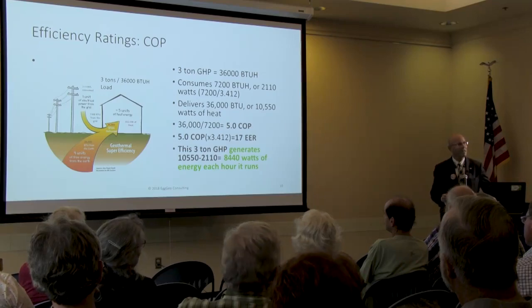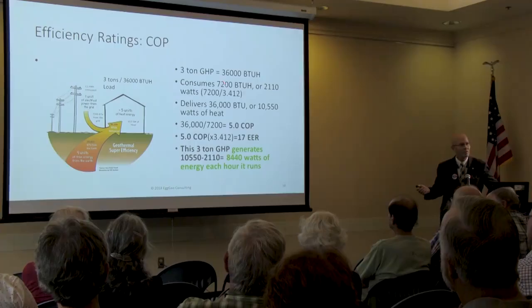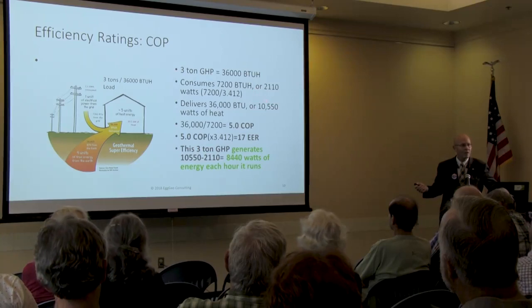In air conditioning and heating, 1 ton of air conditioning is 12,000 BTUs. Interestingly enough, 12,000 BTUs, or the term ton, comes from how much cooling effect or heat can be absorbed by 1 ton of ice melting. Literally 2,000 pounds of ice melting is equivalent to 1 ton. That's where it came from. So a 3-ton heat pump is rated at 36,000 BTUs. To do that 36,000 BTUs of heating, it only uses 7,200 equivalent BTUs of electricity, or 2.1 kilowatts.